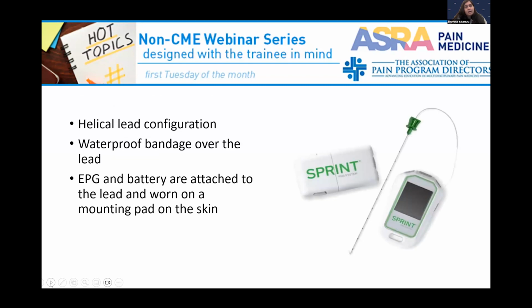Next slide, please. So with Sprint, it's a lead which is placed internally with an external connection that comes out. It's not completely tunneled under the skin. The lead has a helical configuration and has a waterproof bandage that you wear over the lead when it's connected to the EPG and the battery. And for this device, a minimum of 2 centimeters of the lead should be implanted under the skin to minimize migration risk. The length of the lead in the introducer itself is about 12 centimeters, and it allows fairly significant flexibility in how far from the target site that you want to start it.